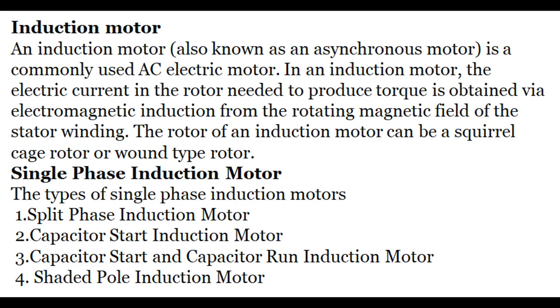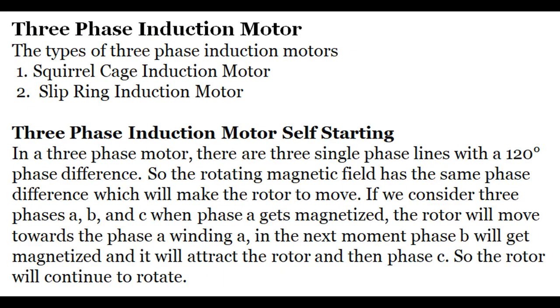Types of single phase induction motors: 1) split phase induction motor, 2) capacitor start induction motor, 3) capacitor start and capacitor run induction motor, 4) shaded pole induction motor. Types of three phase induction motors: 1) squirrel cage induction motor, 2) slip ring induction motor. A three phase induction motor is self-starting: with 3 single phase lines at 120 degrees phase difference, the rotating magnetic field causes the rotor to move toward each phase in sequence — A, B, then C — causing continuous rotation.